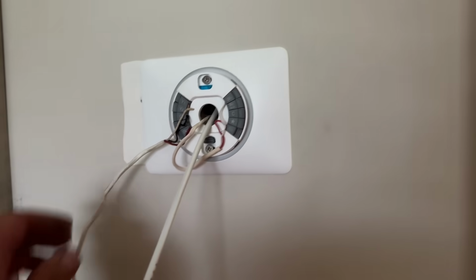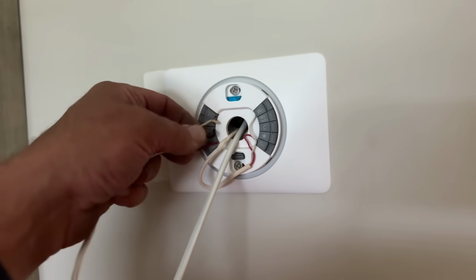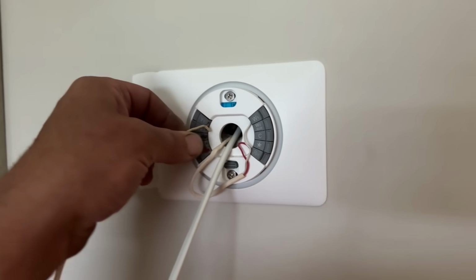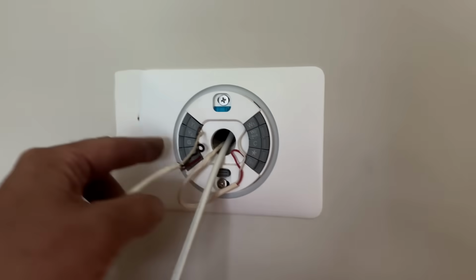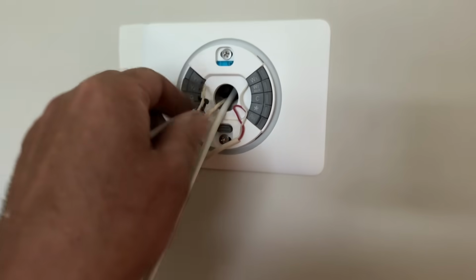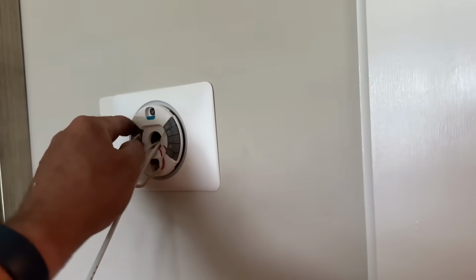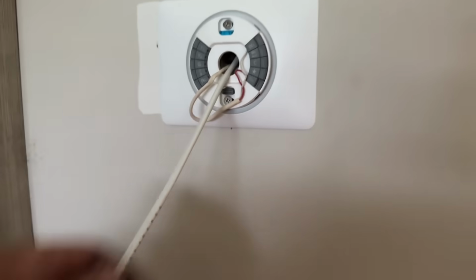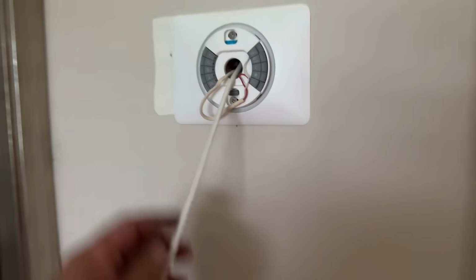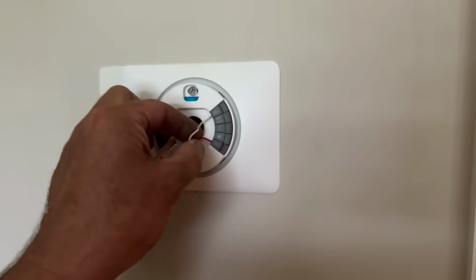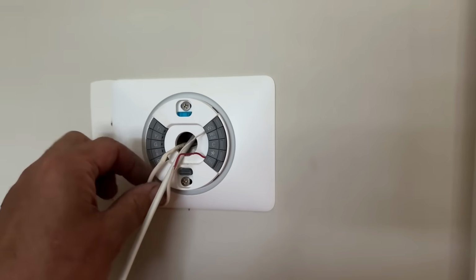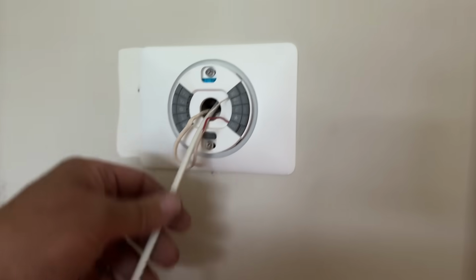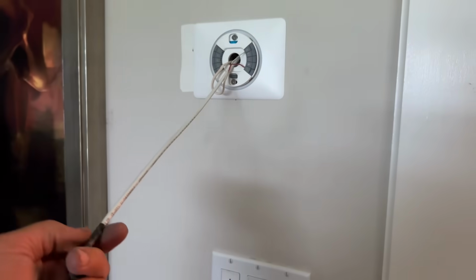All right, we had to run a new wire because there's only 3 wires going to the thermostat from the air handler, which was Y1, G, and RC, going to this hockey puck. So we just ran a new 5 wire. I don't need more. There's a separate RH and W here for hydronic heating. So we're gonna wire up the air handler with OB.